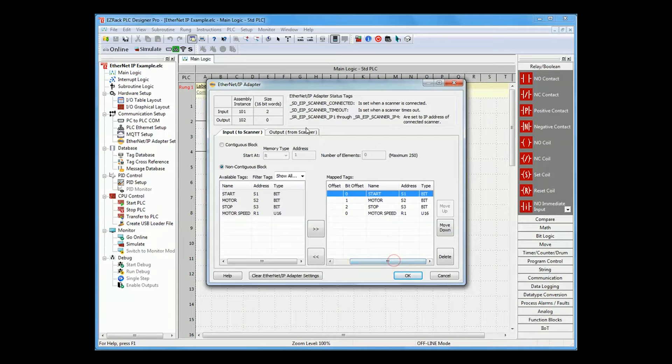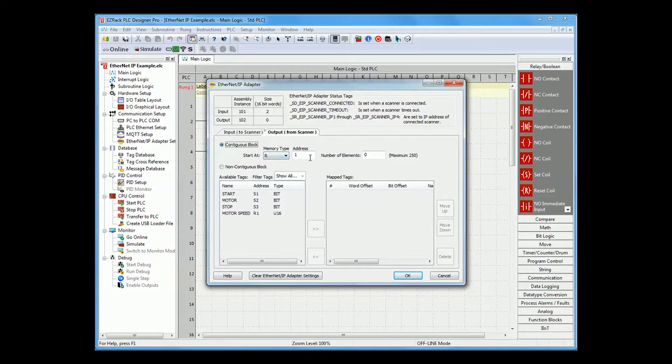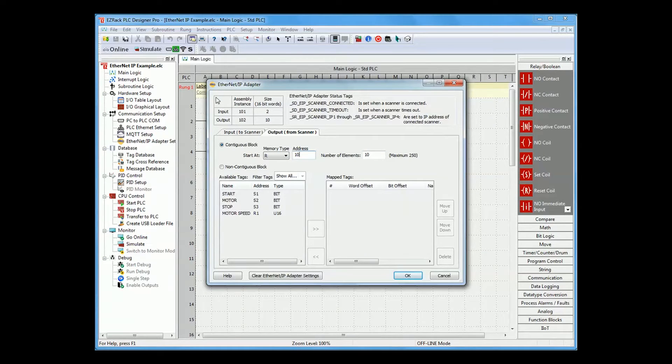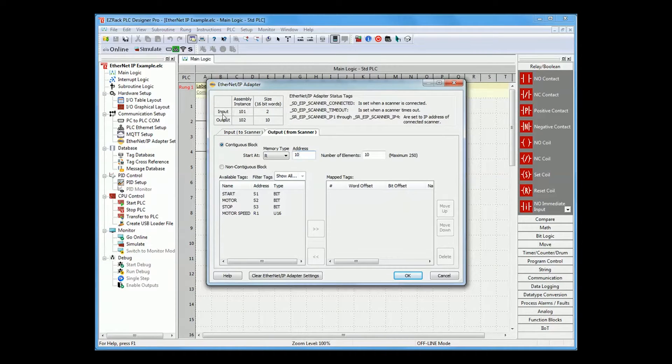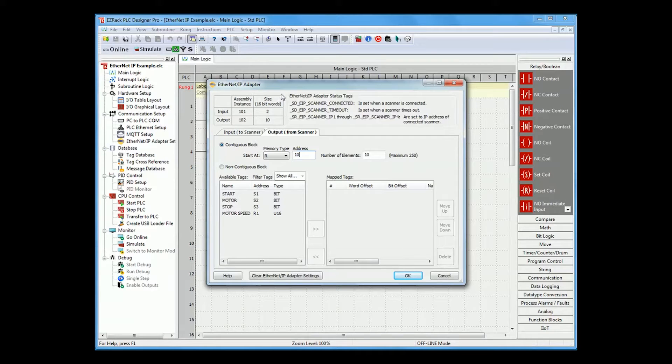Also, you can configure the output from the scanner. For myself, I'll just use a contiguous block starting from register R10 and I will do 10 elements. Now, as you see up here, you will have some information about the assembly instance for input and output and the size in 16-bit words. This is the information needed for the adapter for the scanner setup.